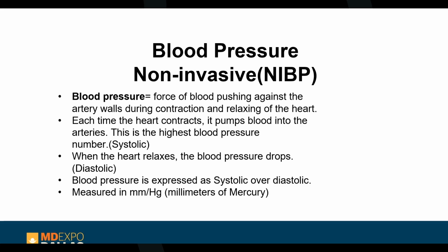I remember back in the old days, when I was younger, I had to replace a BP pump on an NIBP. It wasn't pumping up to high enough pressure to take a blood pressure. I haven't seen it as much on the newer BP monitors. Well, I'll take that back, there are a lot of failures on the X3 BP pumps. They don't pump up to high enough pressure. I had one that I thought I'd save and hook up to a battery or something, to use as a bike pump on my bicycle so I don't have to pump it myself.